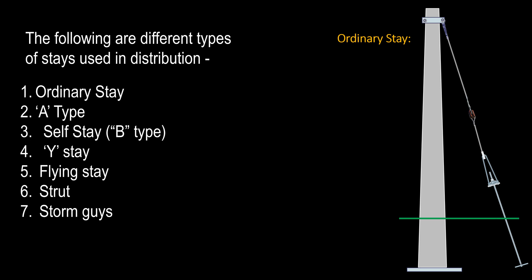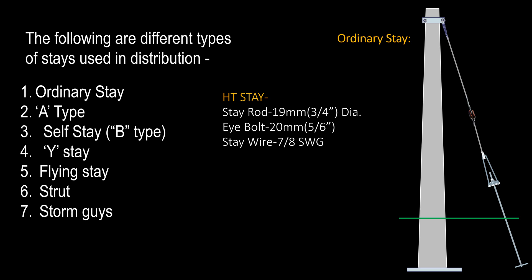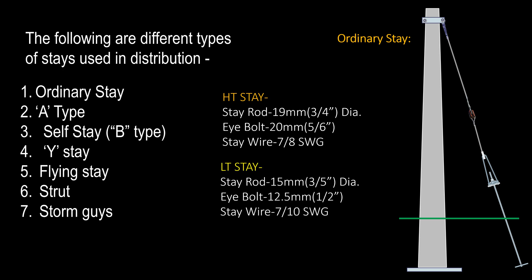Ordinary Stay: This type of stay is generally used in the distribution system. The size of stay rod, turnbuckle, and stay wires are to be used as per the line tension. Generally for HT lines: 19 mm or 3×4 inch diameter stay rod, 20 mm or 5×6 inch size eye bolt, and 7×8 SWG size stay wires are used. For LT lines: 15 mm or 3×5 inch stay rod, 12.5 mm or 1/2 inch eye bolt, and 7×10 SWG stay wires are used. The stay insulator shall be used at a vertical height of 3 m (10 ft) from the ground.